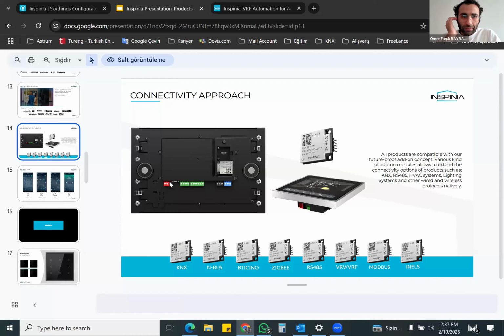All devices might be powered with external 24 volt DC external power supply, or PoE, except the mini server which is passive PoE. Other devices, the 8-inch, 10-inch devices, and 4SQ, also have PoE, active PoE. No need to use both power options. If you have PoE function in your network switch, we don't suggest using external power supply at the same time, you need to choose one of them. If you already have a 24 volt external power supply, we don't suggest using the PoE function in your network switch.